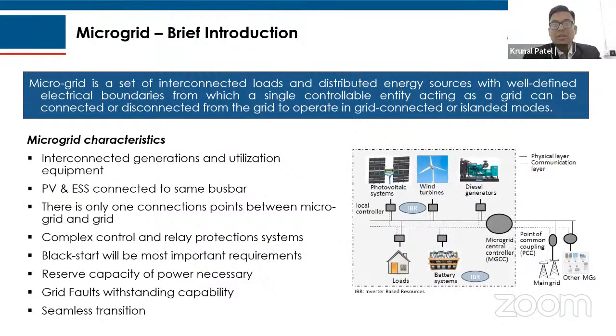A complex control and relay protection system is required. There is black start, which is the most important part in any microgrid requirement. Reserve power capacity is also needed, because in case of any black start issues, the reserve power capacity will help to start the microgrid. Then there is grid fault withstand capability, and one of the most important, a seamless transition between on-grid and off-grid scenarios. These microgrid characteristics are very important for the inverters to adapt to. So inverter technology should be adaptable to these microgrid requirements.